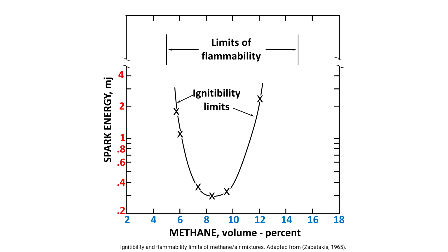But it's kind of a U-shaped curve. If you plot the concentration along the horizontal axis and the minimum energy required to ignite it along the vertical, it's kind of a U-shaped curve for most fuels. Right around the middle of that range for most materials, it reaches a minimum. And that means it's most sensitive to even weak ignition sources. But when it goes, as I said, that's your ideal mixture. Maximum flame velocity, maximum explosive potential, and the highest temperatures.